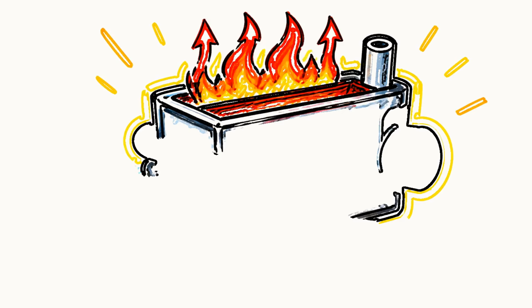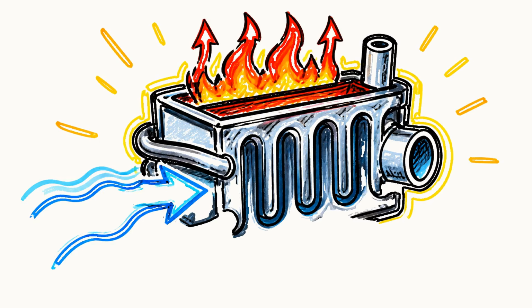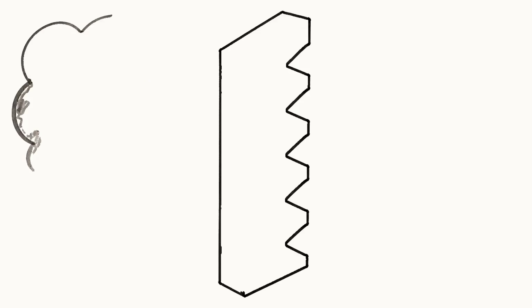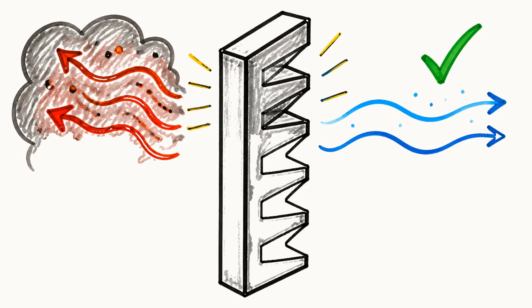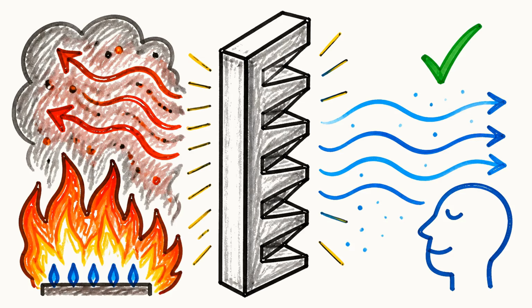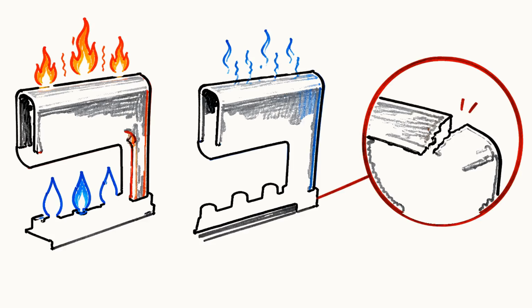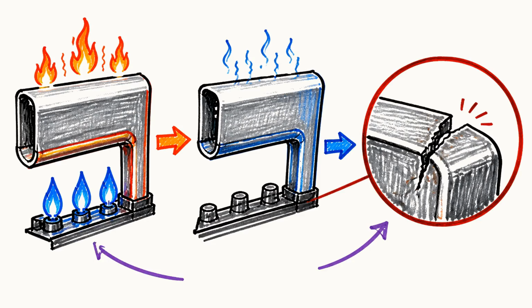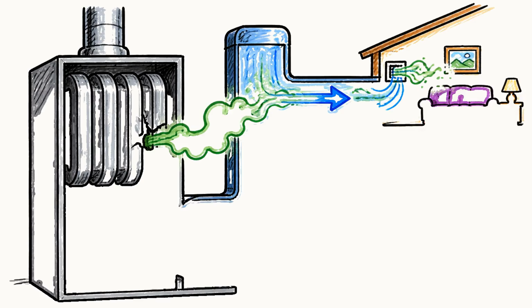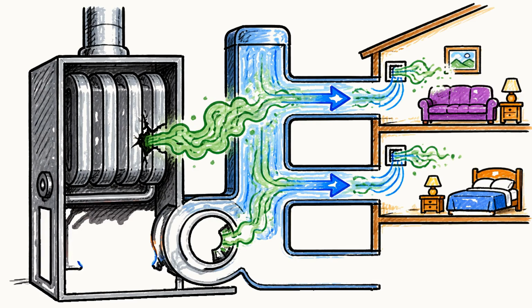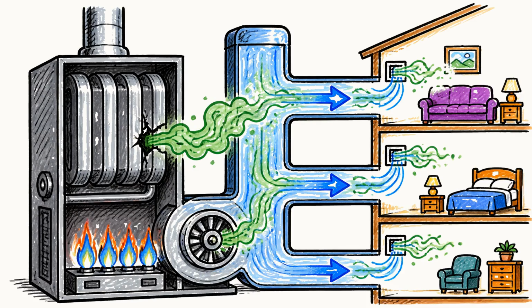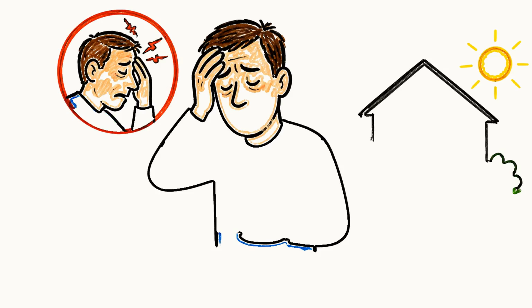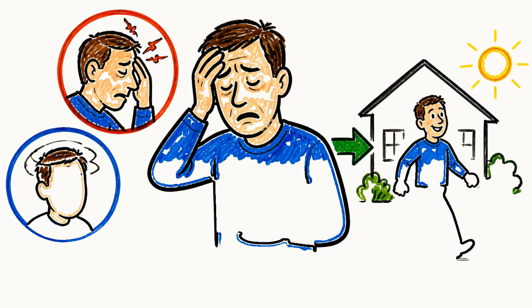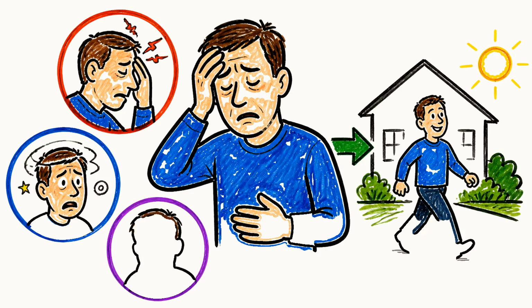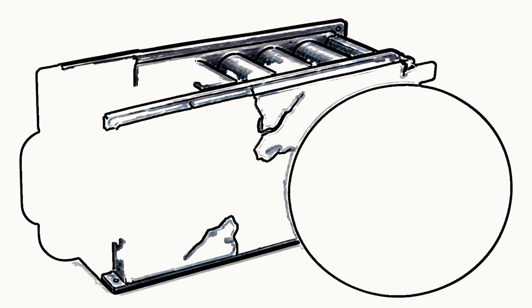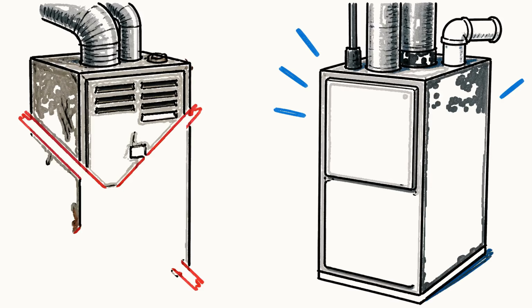Now back to that heat exchanger, because it is the one part of all this that is genuinely worth taking seriously. Remember, it is the metal wall that keeps the fire and the exhaust separate from the air you breathe. Over many years of heating up and cooling down, that metal can fatigue and crack. When it does, combustion gases, including carbon monoxide, can slip into the air your blower is circulating through every room. You cannot see carbon monoxide, smell it, or taste it, and the early symptoms feel just like the flu, headaches and dizziness and nausea that often ease up when you leave the house. A cracked heat exchanger cannot be patched, the furnace has to be replaced.